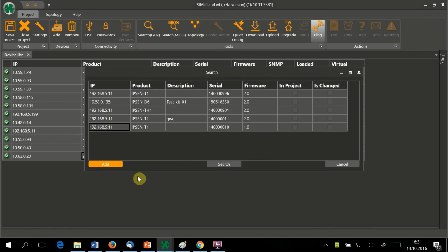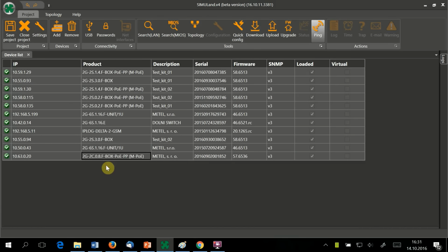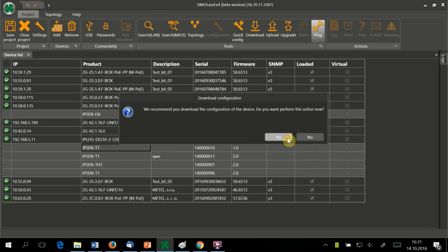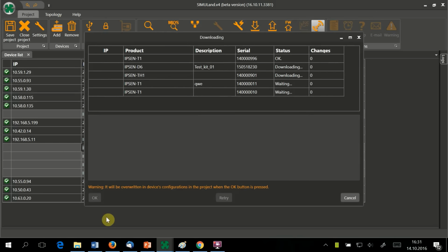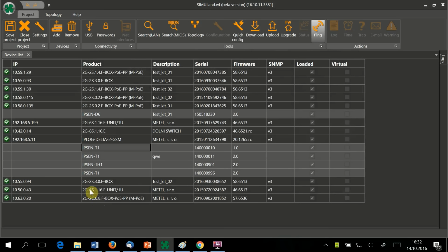Projects include switches and control units, which are identified by an IP address, and MIOS I/O modules and sensors connected via the RS-485 bus. To be configured, first, the device must be searched, which only takes one click. A point of interest is that while MIOS modules are connected to the RS-485 bus, they can be monitored and configured by SNMP or Modbus protocol.